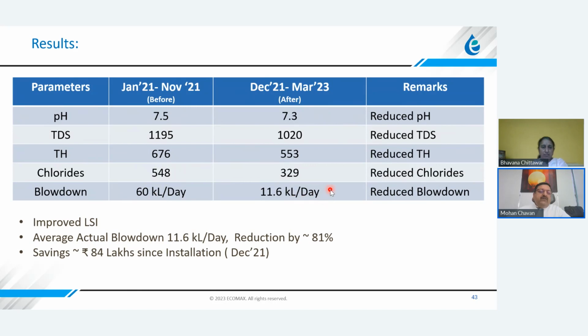Okay? And of course, LSI and other water parameters have improved, and they got a lot of benefits on the process side. So the actual blowdown is about 11.6 KL per day, which is almost 81% reduction in the blowdown water consumption. And they saved almost 84 lakhs since December 21.